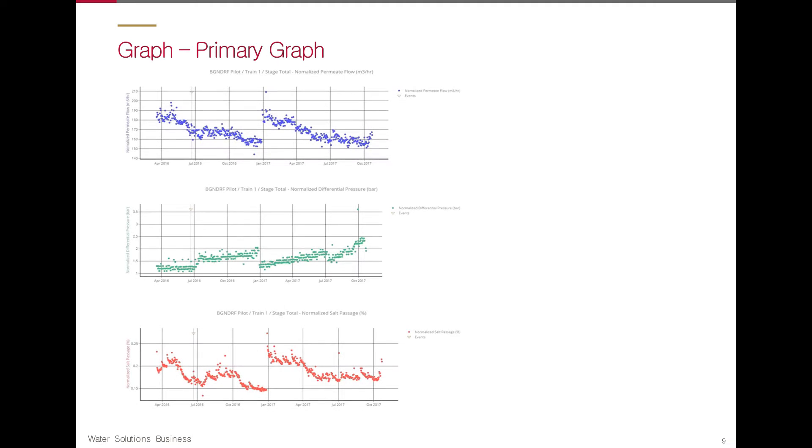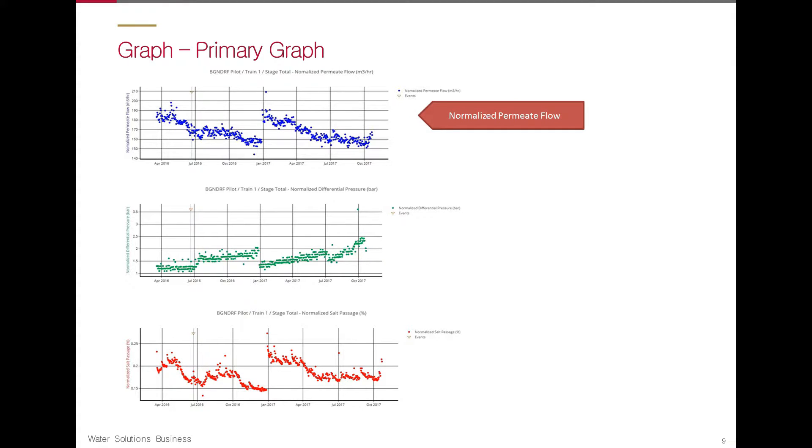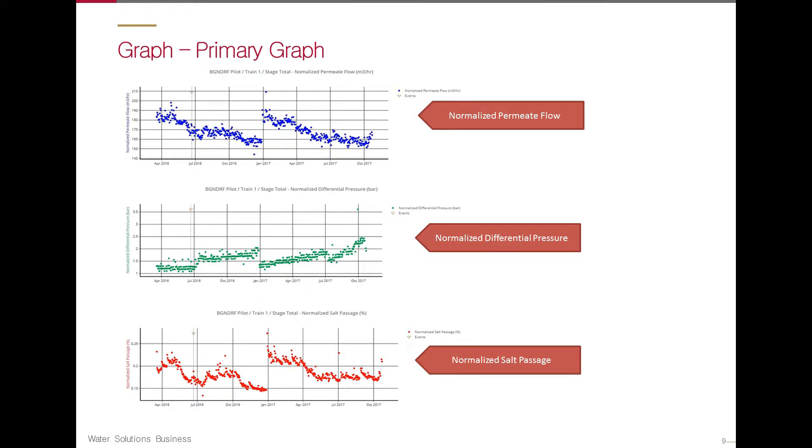With QC, you can quickly generate the primary performance graphs, which are normalized permeate flow, normalized differential pressure, and normalized salt passage.